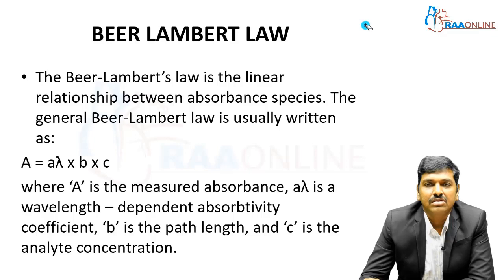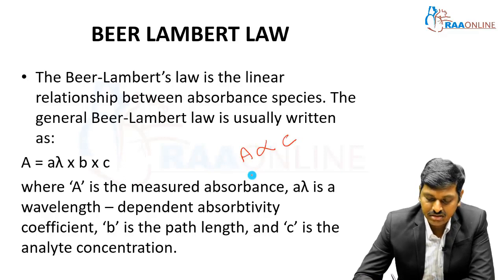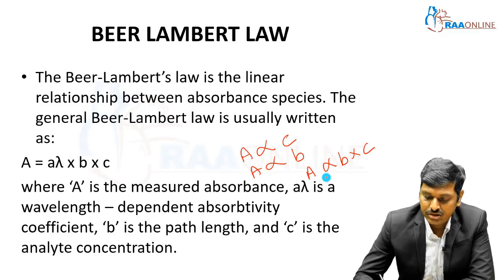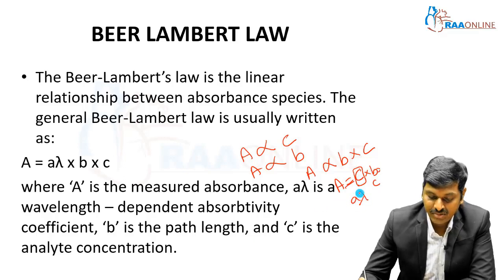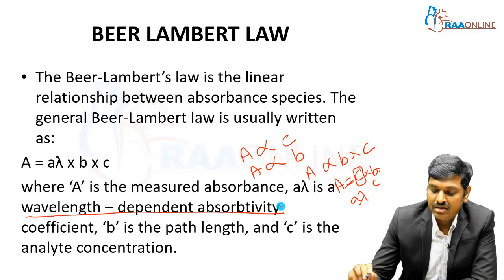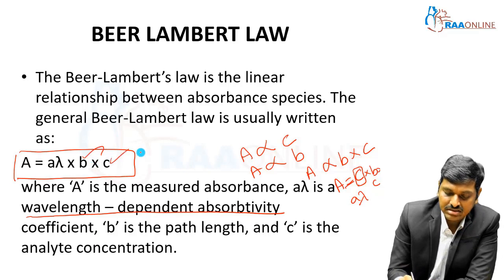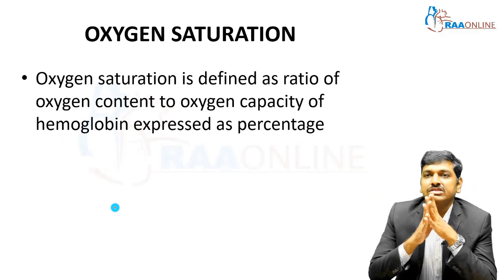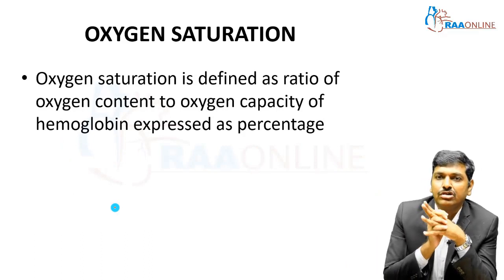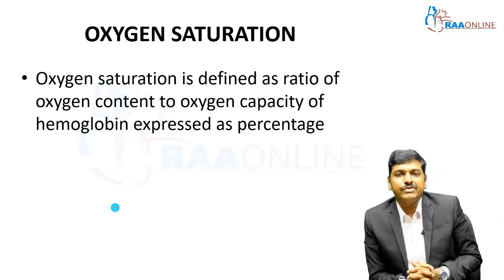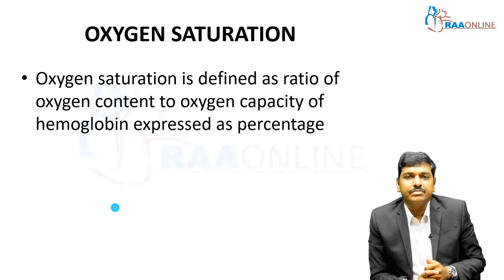Combining these, the Beer-Lambert law expresses a linear relationship: absorbance A is proportional to both concentration and path length. Introducing a constant, the equation becomes A = A-lambda × B × C, where B is the path length, C is the concentration, and A-lambda is the wavelength-dependent absorptivity specific to each substance. Oxygen saturation is defined as the ratio of oxygen content to the oxygen capacity of hemoglobin expressed as a percentage — for example, 14 out of 15 grams saturated gives approximately 93–94%.